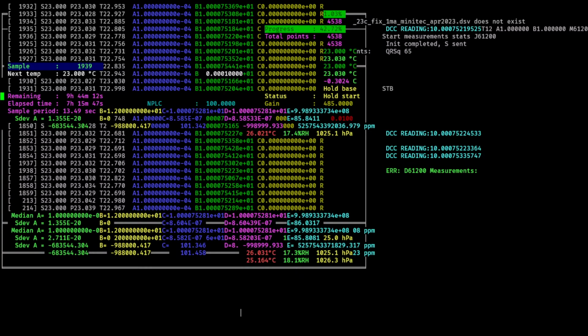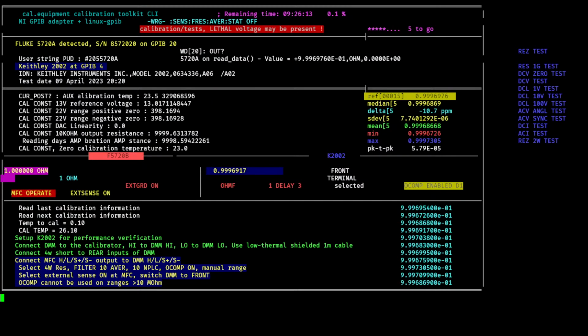And there is some resistance measurement in the background. The interface got messed up, but it's still logging, so I'm not going to stop it. And this is a test of resistance. So here is 1 ohm measurement. Reference is 0.9996976. Just calibrated yesterday. And now actually reading is 9.9 ppm off. It's too low compared to expected value, but this is still well within specification of Keithley 2002, even 24-hour specification.